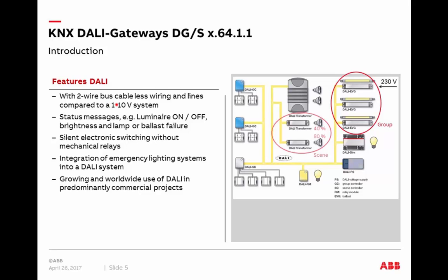DALI is replacing more and more the existing 1-to-10 volt technology, and nowadays it is mainly used in commercial projects. It is an intelligent system — you cannot only control the lamps, you also have status messages such as whether a light is on or off, and the brightness value can be sent back to the system. A very important feature is detecting any lamp or ballast failure for each DALI lamp connected. DALI ballasts have no relays — it is electronic only inside, so operation is free of noise. DALI can also be integrated with emergency lighting systems. DALI is a growing worldwide system for lighting control, mainly for commercial projects.